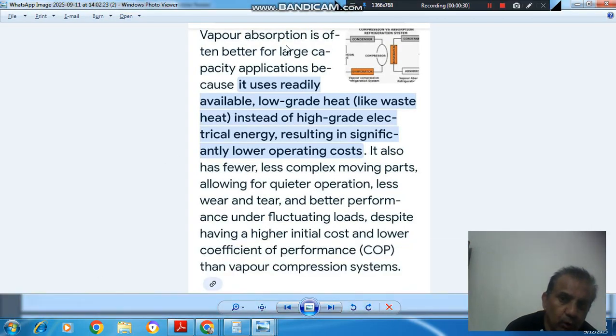The explanation is that vapor absorption is often better for large capacity applications because it uses readily available low grade heat, like waste heat, instead of high grade electric energy, resulting in significantly lower operating cost. It also has fewer, less complex moving parts, allowing for quieter operation, less wear and tear, and better performance under fluctuating loads, despite having a higher initial cost and lower coefficient of performance than the vapor compression system.